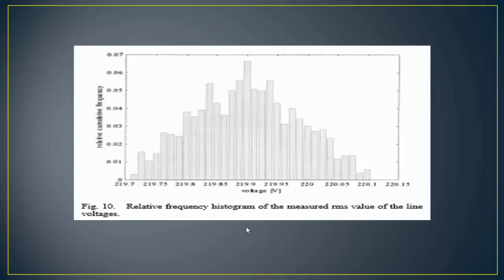Fig 10 shows the relative frequency histogram of the evaluated voltage RMS value. The relative standard uncertainty is 0.04%. A similar histogram was obtained for the current RMS value with a relative standard uncertainty of 0.054%. When the harmonic components of current are considered, the relative standard uncertainty becomes 0.15%.